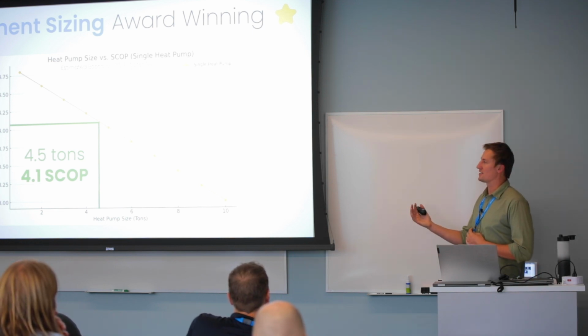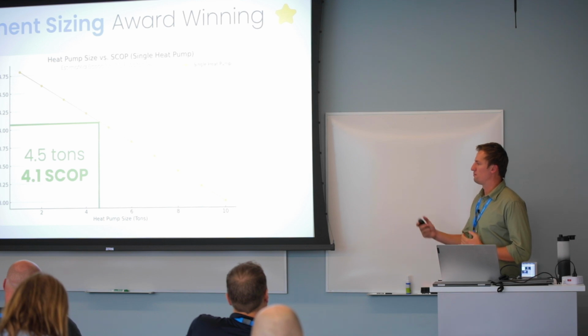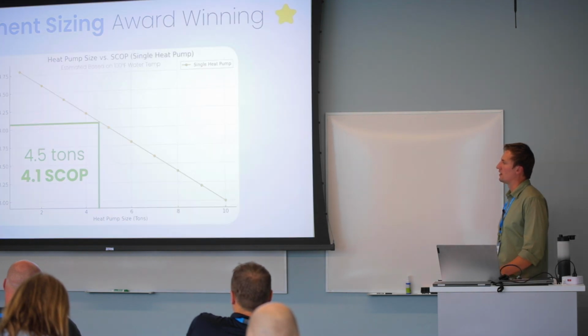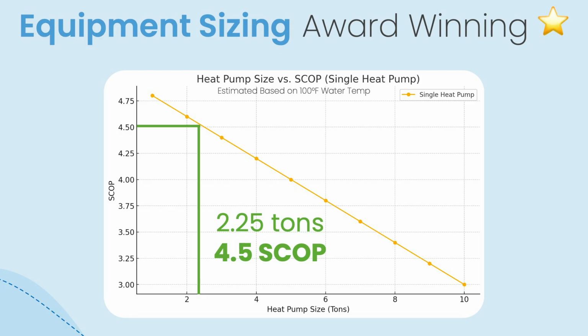Yeah, and I suppose if you're doing a new build, the cascade, sharing the load makes sense, but if you've got a gas system that does a lot of it, you can just have a supplementary heat pump as well, or the other way around. But I suppose just to demonstrate, if you did put them together, very simple, reduces the load by half, assuming they're doing 50-50, and as you can see here, got a 4.5 SCOP. So turning every 1 kilowatt of energy into 4.5 of heat output, and I suppose remembering this is the 450% efficiency that we mentioned at the beginning.